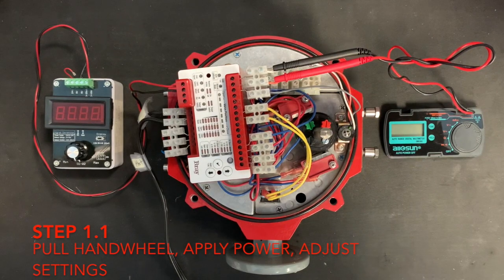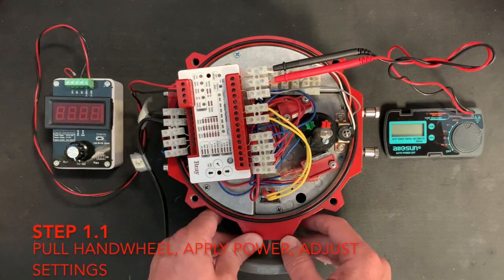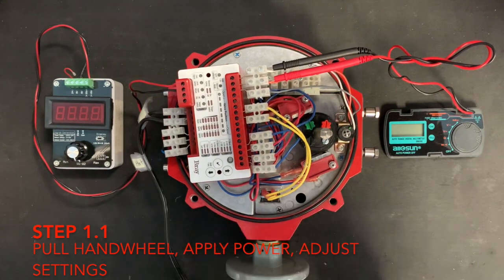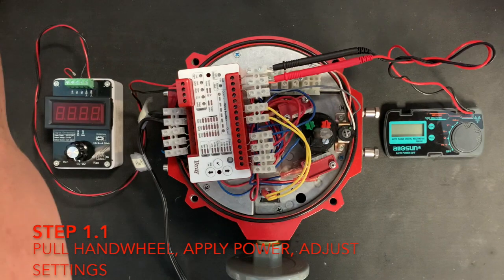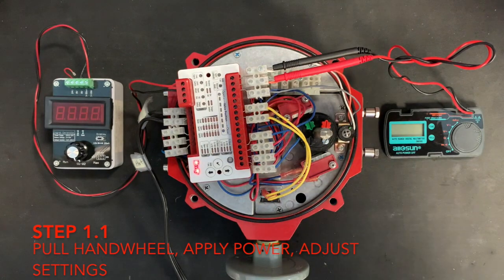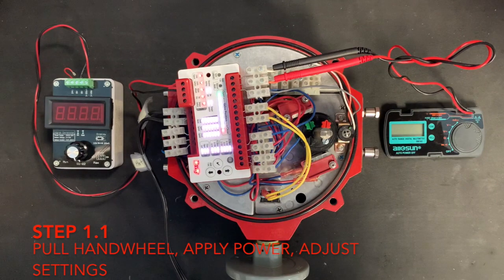Pull the hand wheel to disable the electric motor. Apply power to the terminals. For servo NXT electronic modules, adjust display settings using the arrow keys and check mark.